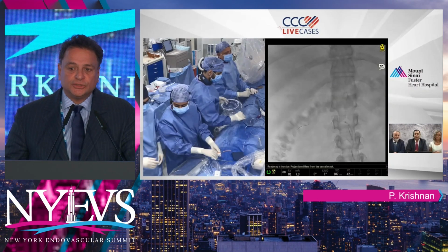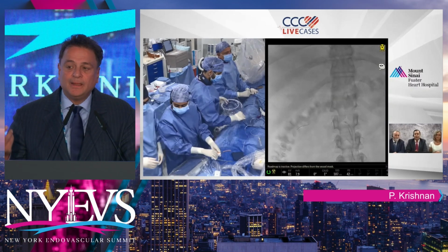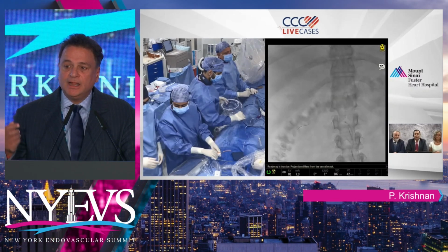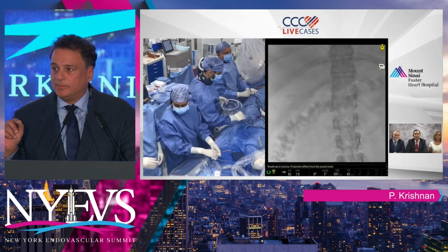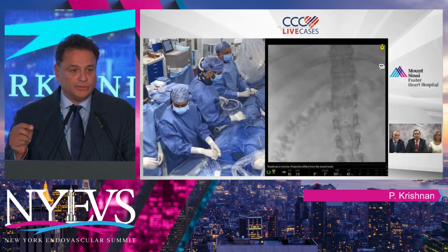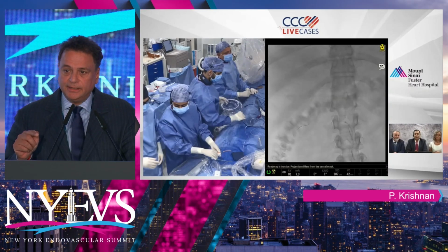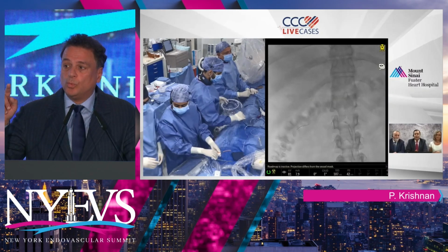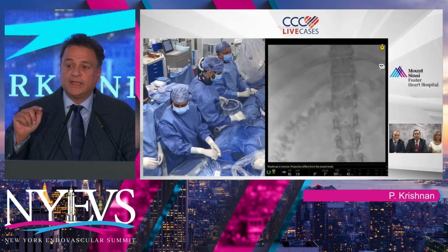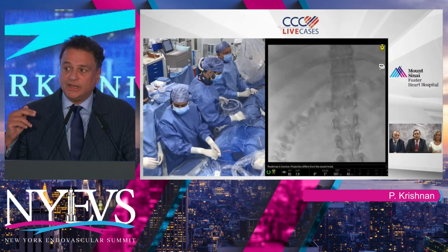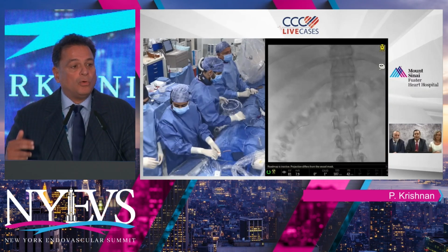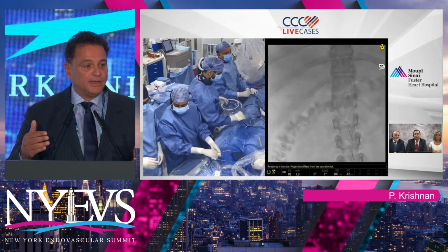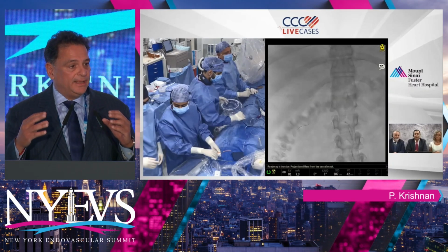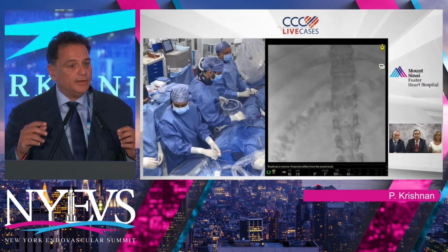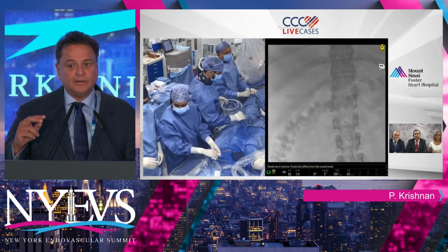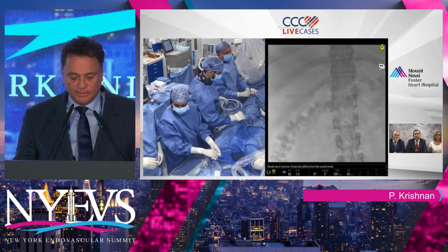As Dr. Butt showed you, the spiral catheter has multiple electrodes on the catheter. And the handle, which Dr. Sharma had in his hand, has numbered buttons for each one of those points, I should say, for electrodes. As the device is introduced, you will start to see a waveform on the machine, and the machine will look at the impedance, which tells you how the contact with the vessel wall is in order to deliver adequate therapy. Unlike the Radiance device or the RECOR device, which has a balloon to oppose it against the wall, here the spiral configuration of the catheter is able to oppose against the wall.